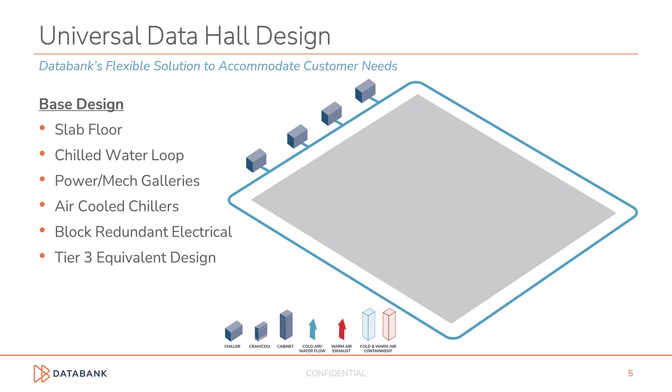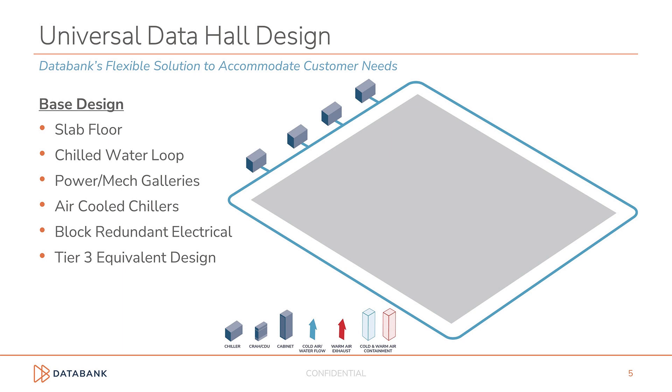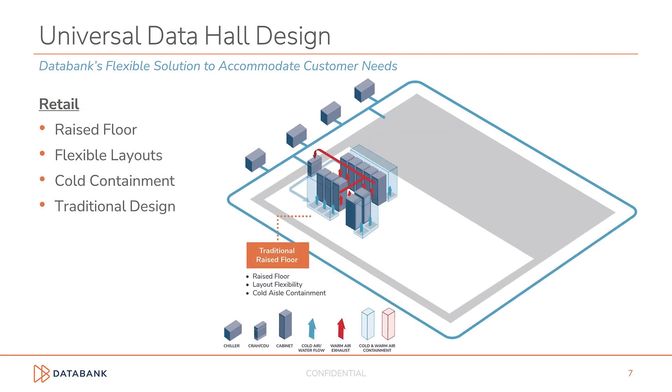This solution accommodates all customer needs, including the increased demand for high-density co-location. We start with a base building designed around slab floor data halls, equipment corridors, block-redundant electrical topology, and an air-cooled chilled water loop with perimeter CRAH cooling. We chose to standardize on air-cooled chillers for both reliability and to avoid the environmental impact of water-cooled solutions. We still use water, but it is contained in a closed-loop system, which wastes very little water compared to traditional evaporative cooling. Our base design can easily accommodate hyperscale deployments that require high-weight cabinets and slab floors, and the universal data hall design also accommodates traditional raised flooring for customers that need a more flexible layout, with power requirements that can be satisfied with cold-aisle containment cooling.